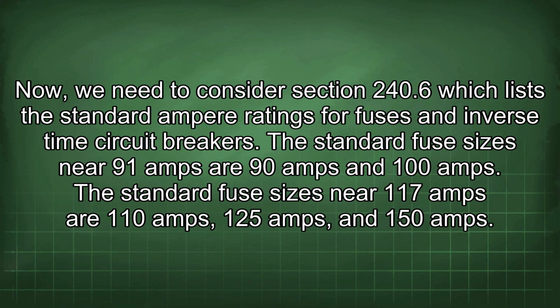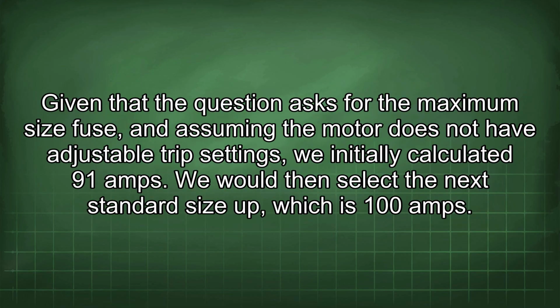Now, we need to consider section 240.6, which lists the standard ampere ratings for fuses and inverse time circuit breakers. The standard fuse sizes near 91 amps are 90 amps and 100 amps. The standard fuse sizes near 117 amps are 110 amps, 125 amps, and 150 amps. Given that the question asks for the maximum size fuse, and assuming the motor does not have adjustable trip settings, we initially calculated 91 amps. We would then select the next standard size up, which is 100 amps.